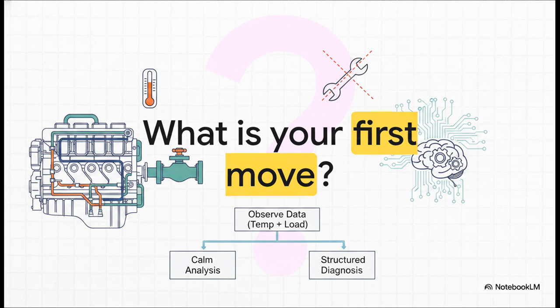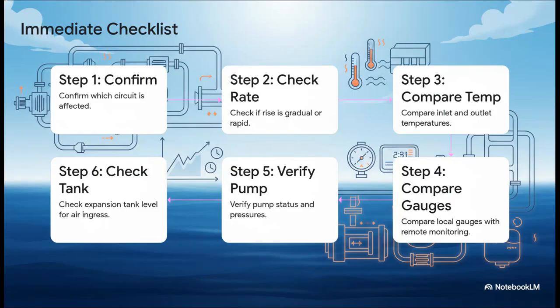What's your very first move? Now, if your gut tells you to grab a wrench or start cracking a bypass valve, you need to fight that instinct. That's how you introduce new problems. You can trap air, you can upset the whole system, and you'll lose the trail. The professional response is calm and methodical. This is your checklist. This is what you do first, every time.